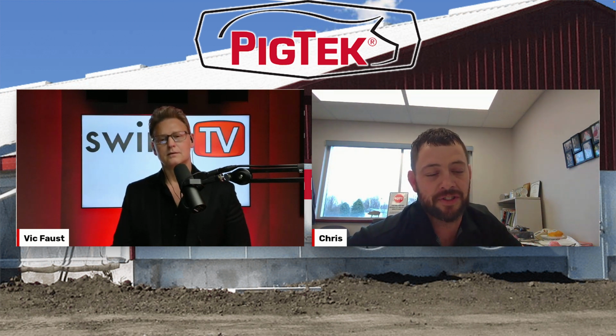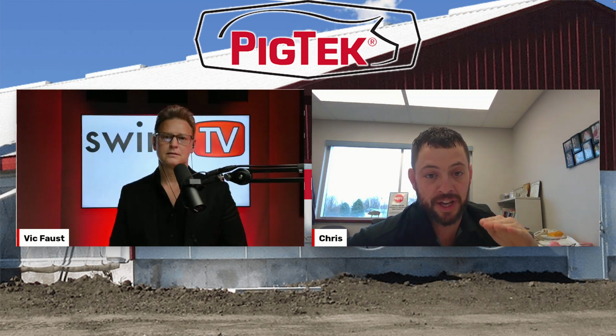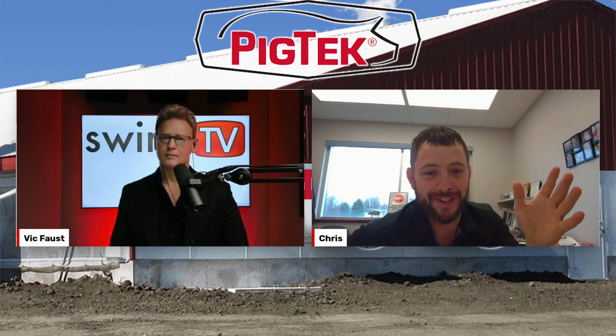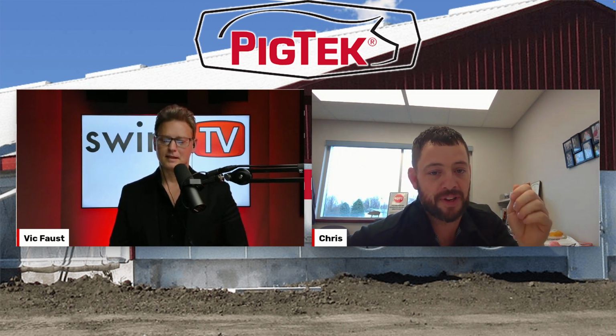Okay, so there are newer technologies, like these permanent magnet motor fans or these truly variable fans, where they actually truly do reduce. When they slow down, they do save you money. So that's the thing when you look at it: having variable fans on the big fans, we try to sell those fans, of course, but that isn't where your bang for the buck is. Your bang for the buck is those fans that are running 24/7.